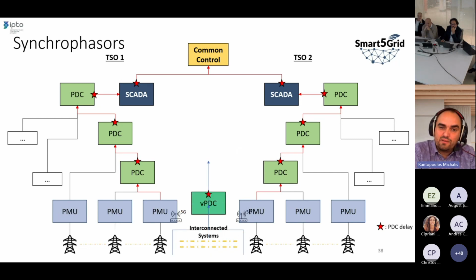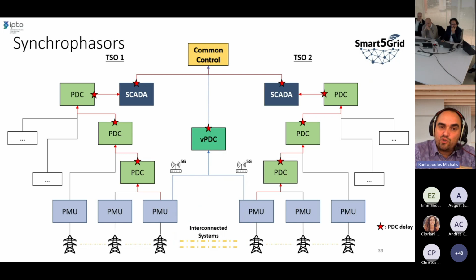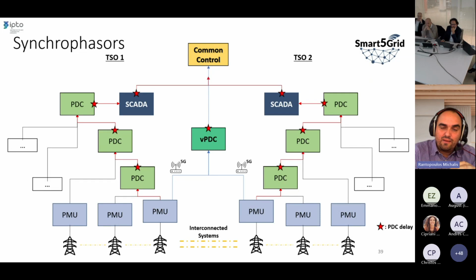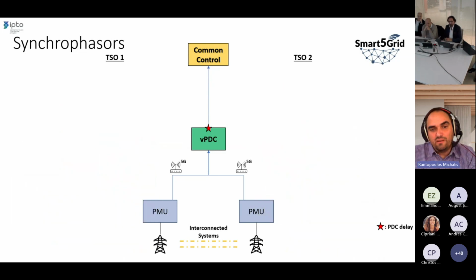So we'll try to simplify this. Please proceed with the animation showing the creation of a virtual PDC and the utilization of 5G networks from two operators, giving us a simple connection. The concentrator gathers readings from multiple points, and 5G ensures that an absolute wait time criteria of 40 milliseconds is kept for correct reading of the measurements from the concentrator. If this value is exceeded, the PDC itself discards those measurements.